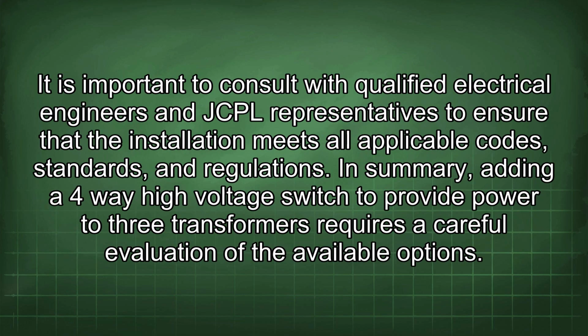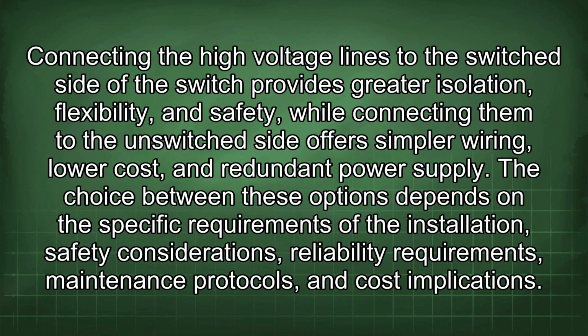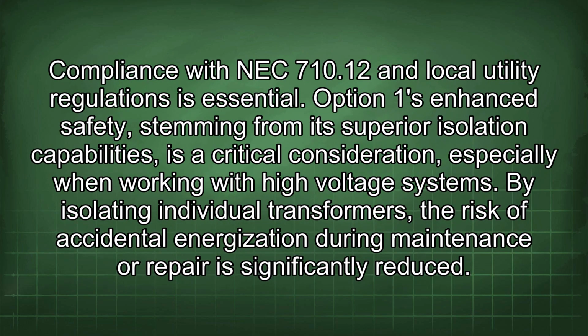It is important to consult with qualified electrical engineers and JCPL representatives to ensure that the installation meets all applicable codes, standards, and regulations. In summary, adding a 4-way high-voltage switch to provide power to 3 transformers requires a careful evaluation of the available options. Connecting the high-voltage lines to the switched side of the switch provides greater isolation, flexibility, and safety, while connecting them to the unswitched side offers simpler wiring, lower cost, and redundant power supply. The choice between these options depends on the specific requirements of the installation, safety considerations, reliability requirements, maintenance protocols, and cost implications. Compliance with NEC 710.12 and local utility regulations is essential.